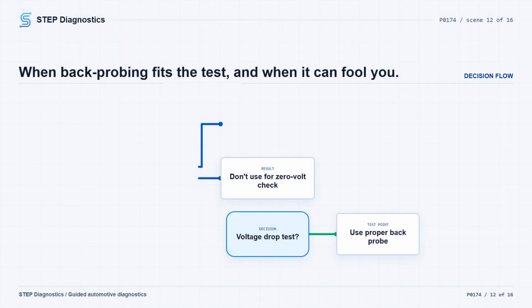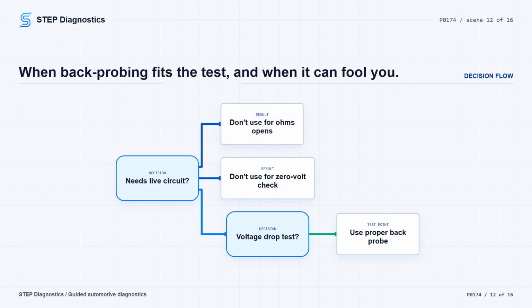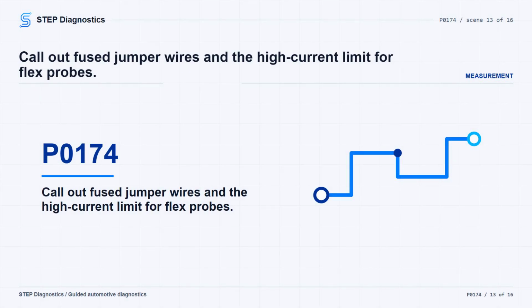Back probing is only for cases where the circuit must be tested under real operating conditions, or where voltage drop has to be measured. For voltage drop work, expect less than 5% of circuit operating voltage. Use back probes made for the job, and do not force probes into connectors. Do not back probe for a single point voltage check when 0 volts could be a valid result, because a bad probe contact can look the same as 0 volts. Do not back probe continuity or open circuit checks with an ohmmeter either, because a bad contact can look like an open.